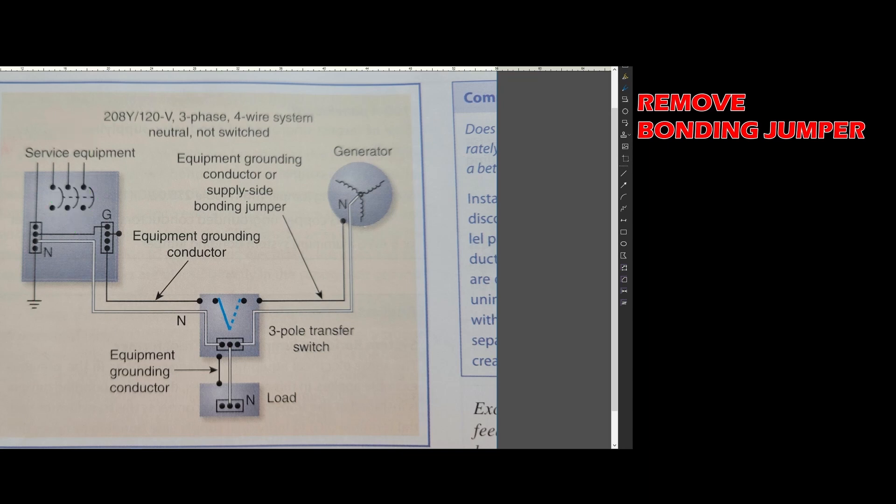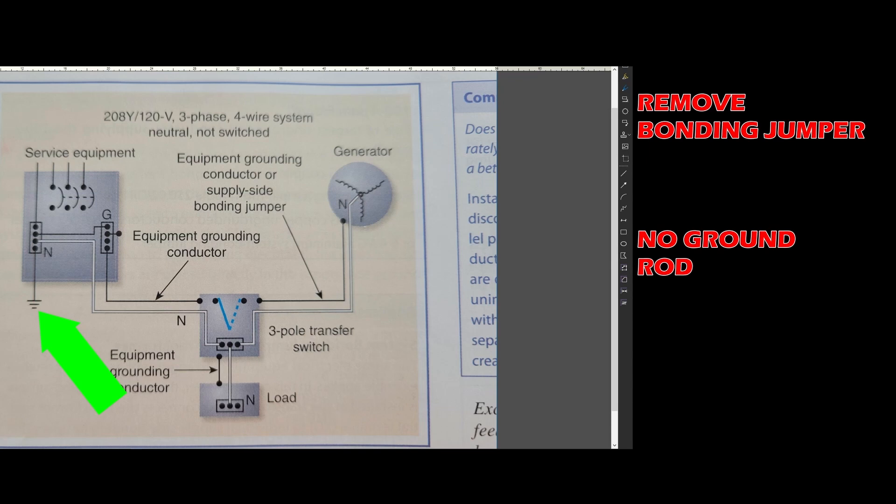The continuous neutral allows you to use your existing grounding electrode here. So no additional ground rod is required by code, as shown in this exhibit.